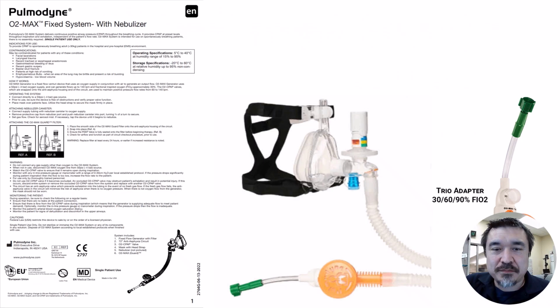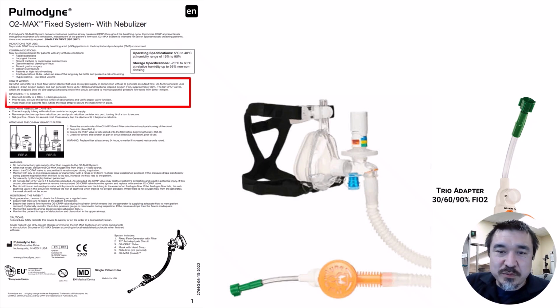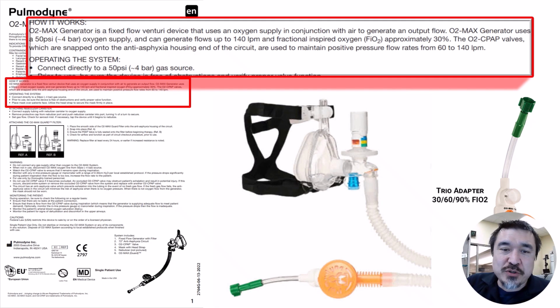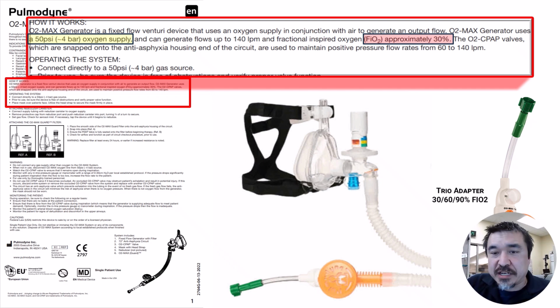Alternatively, we've been carrying the Pulmodyne O2 Max system, but it was pointed out from the field that these are designed to be hooked to the high pressure port. They use a Venturi system to provide a flow up to 140 liters per minute, and it does come with an anti-asphyxiation valve. However, it has a fixed FiO2 of 30%.